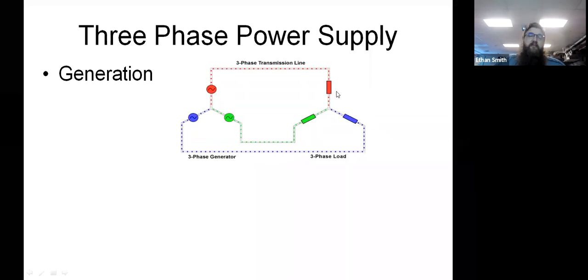In fact, when we talk about single phase power, it's kind of a misnomer because we talk about single phase power as 120 and 208, 230. In reality, 208, 230 is 2-phase power. Okay, if we want to get technical about it. We call it single phase just for simplicity's sake because we don't have the 3 phases and we got to do stuff to start motors.